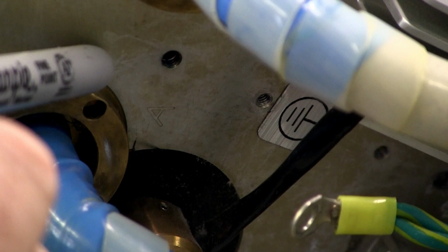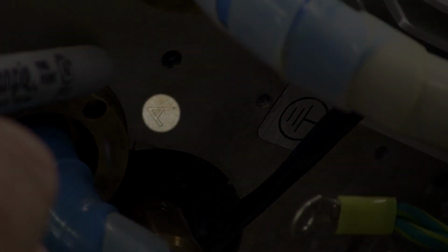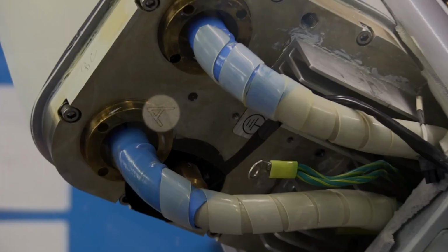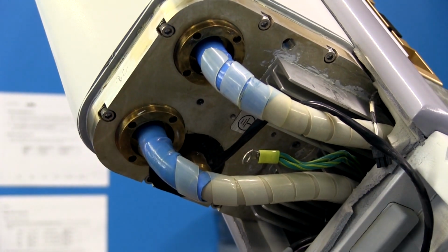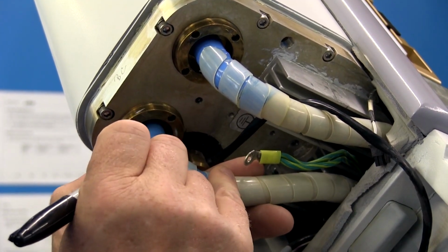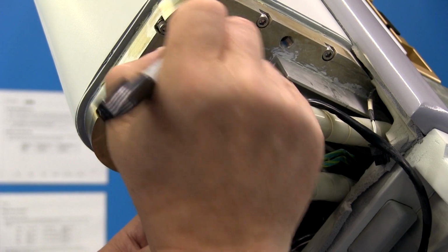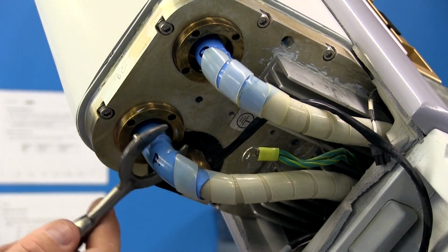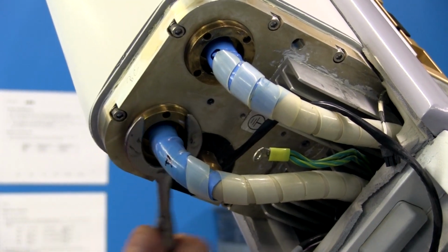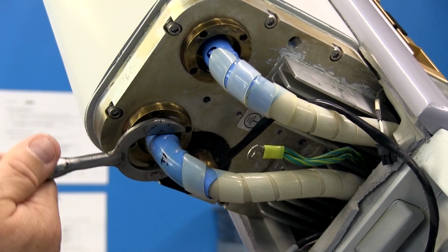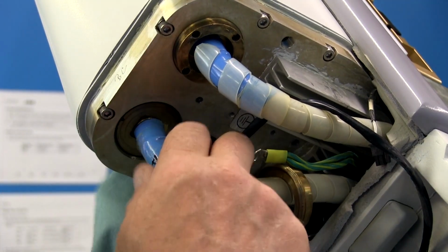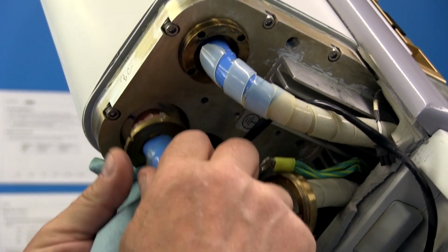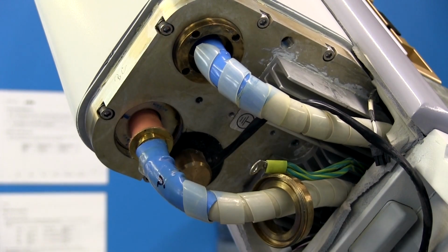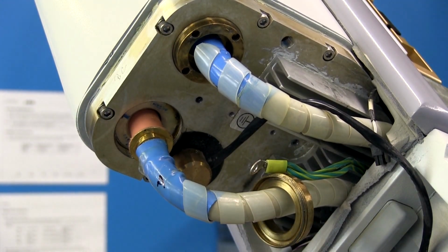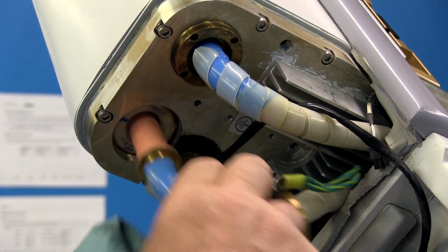There's a little A stamped into the back of the tube here to indicate the anode. We definitely don't want to get these two mixed up, so I always mark them C and A. Then you take your spinner wrench and just loosen these up. You have a little C washer clamp in there that you want to make sure you don't drop. You should have some paper towel available because this is all greased.